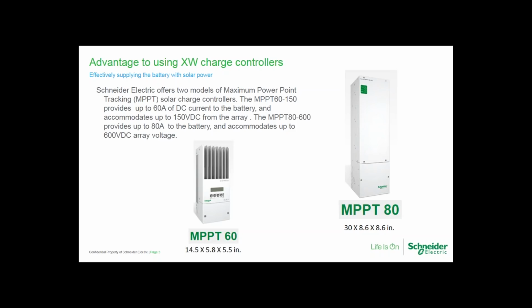So going back into enhanced grid mode, when you're using our charge controllers with our inverters, you set the grid support voltage higher than the bulk voltage by at least 2 volts. And what that does is it tells the XW to follow the output of that charge controller. So it only uses what's available above a fully charged battery to support the load. It does a better job of keeping the batteries full and ready for a power outage.